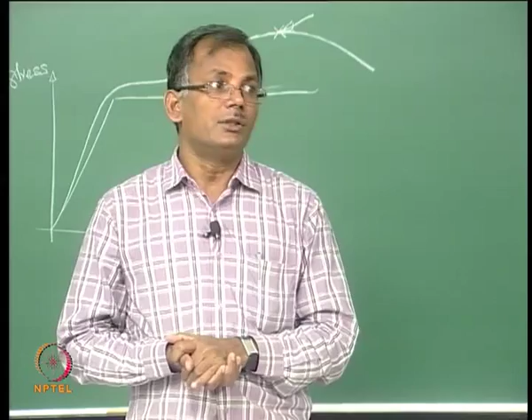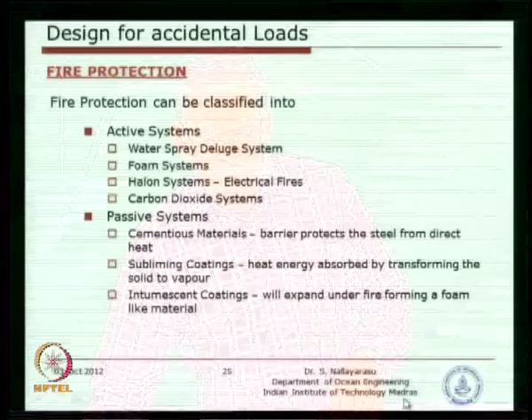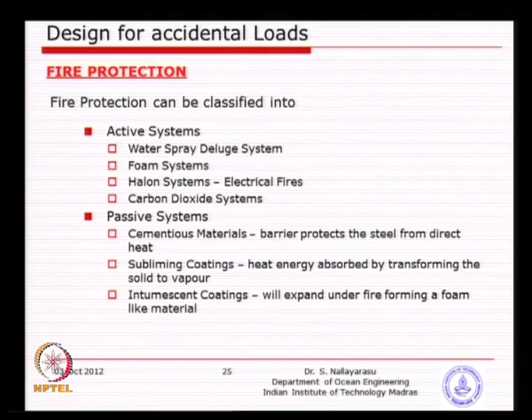The intumescent coating will expand under fire, forming a foam-like material, just like our foam. So, it gives a semi-solid protection between the fire and the steel, a kind of thick material, but not so thick, just a foam-type material. For both of them, the original thickness will be very small, 5 to 10 mm maximum, and the density is lower than concrete. So, you have similar characteristics achieved by a smaller thickness, less weight, but slightly increased cost. So, that is where we look at either subliming coatings, normally not used in many facilities, or intumescent coating, which is well preferred because it has been in use for several decades. If you go through the net, you will find so many vendors with different chemical compositions.